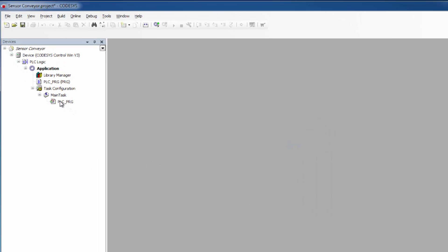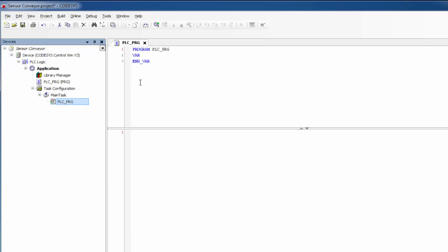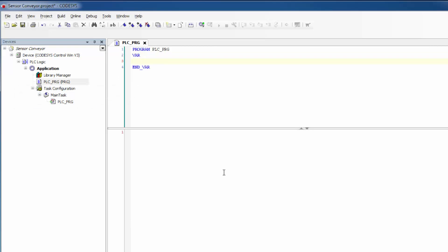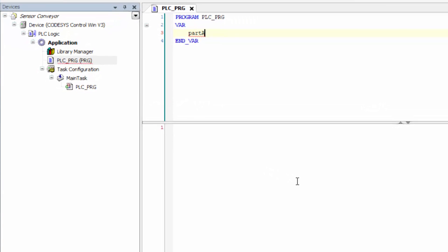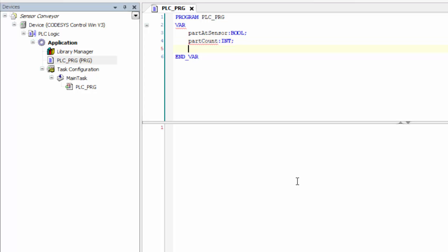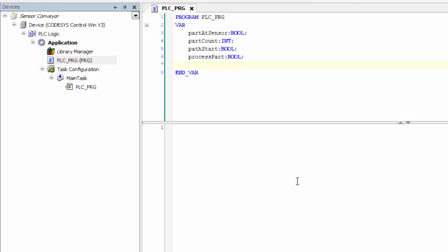I'm going to be using structured text to set up the program. In the devices pane we can see our program, so let's double-click this and create a simple program with some local variables. We want to know if a part is at a sensor — so partAtSensor, type Boolean. We want to count how many parts reach that sensor — type integer. We want to start or stop a conveyor path — pathStart, type Boolean. We'll add processPart as a trigger, and process_time as a TON timer.